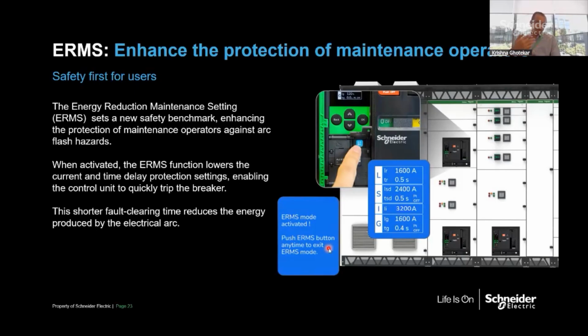So unfortunately, while he is working on, let's say, a capacitor panel, UPS panel, or any other maintenance he is doing, or some other work he is doing in the electrical room, and suddenly there is an arc flash. Thanks to this ERMS mode, the breaker will not wait for the protection settings you have set, like the time delay on TSD or ground fault and so on. Breaker instantaneously goes to the minimum setting and it will trip the breaker, so that the impact of the arc flash is minimal on the operator who is working in the vicinity. So it's much safer for them.